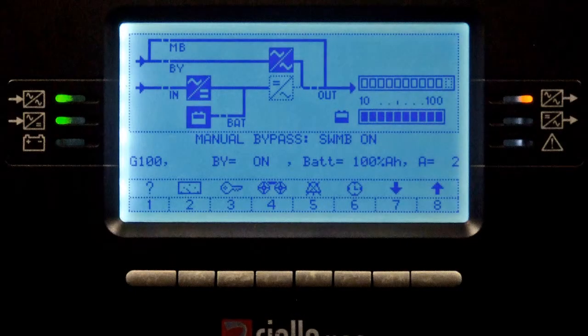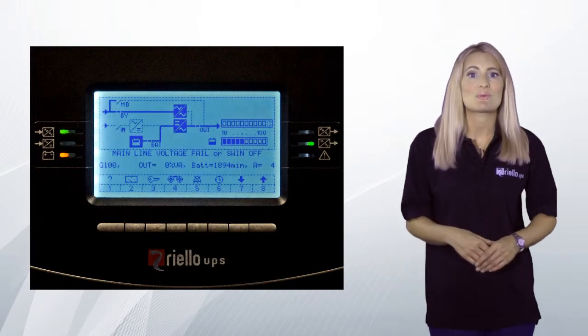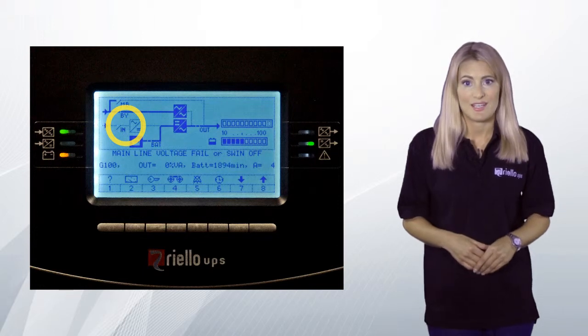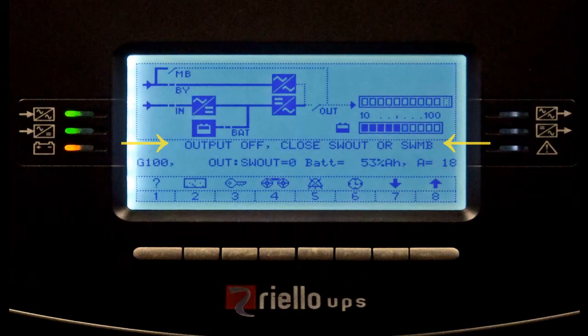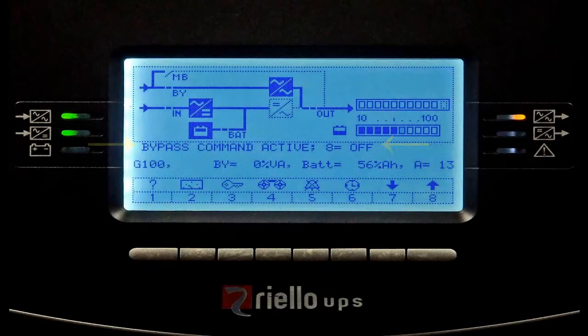This is the UPS display screen with the SWMB closed, which is for the internal maintenance bypass. Here you can see that the maintenance bypass switch is closed and the inverter is disabled. This is the UPS display screen that you will see in the event of a mains failure or with the rectifier input switch open — in this example, the rectifier is not operating. This is the UPS display screen that you would see if the UPS output switch was opened. This is the UPS display screen with the system off command active, and this is the UPS display screen with the bypass command active.